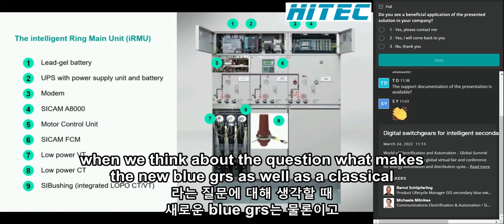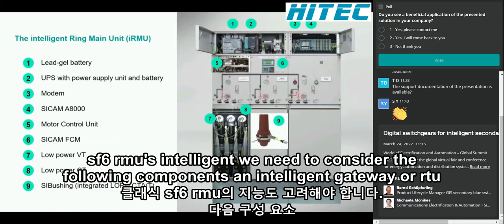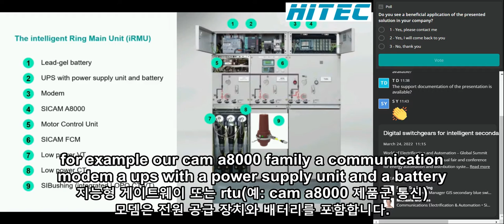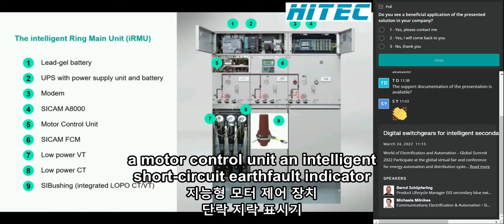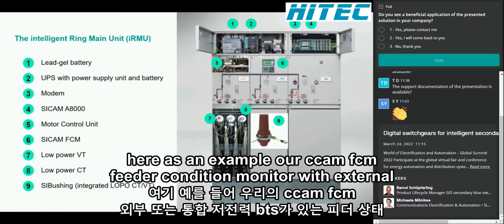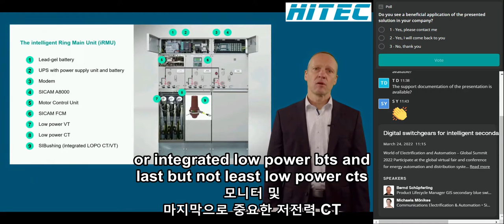When we think about the question, what makes the new Blue GIS as well as the classical SF6 RMUs intelligent, we need to consider the following components. An intelligent gateway or RTU, for example our SICAM A8000 family, a communication modem, a UPS with a power supply unit and a battery, a motor control unit, an intelligent short circuit earth fault indicator, here as an example our SICAM FCM feeder condition monitor with external or integrated low power VTs and last but not least low power CTs.